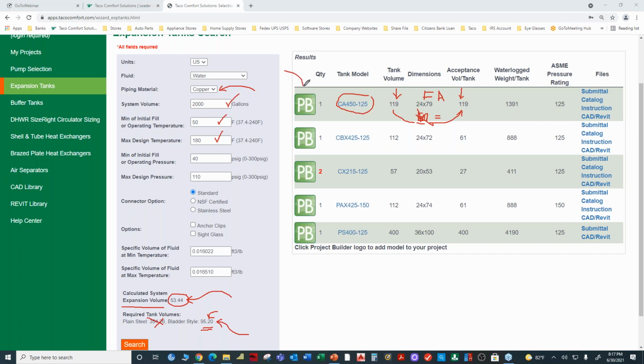The software has made a recommendation. It says for your expansion tank, you can use a CA 450-125. In this case, 125 refers to the pressure rating. The 450 is liters, and that has approximately 119 gallons. So 450 liters, if anybody wants to do the conversion, is approximately 119 gallons. So that will do the job.